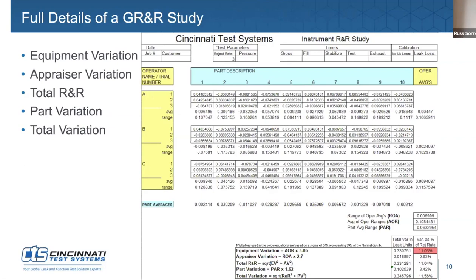So here's a gauge R&R study, some more. Yeah. So this is a full-blown gauge R&R study. Not only is it 10 parts, 3 operators tested 10 times each, it also takes into account test variation and then equipment variation, and also appraiser variation, total R&R, part variation, and then the total variation in the whole system.